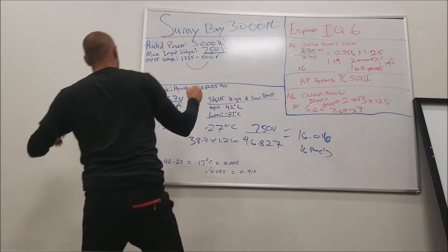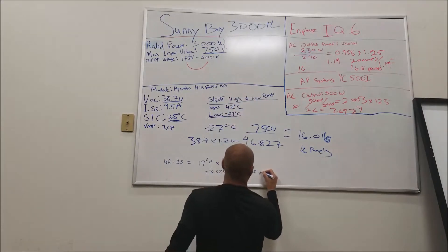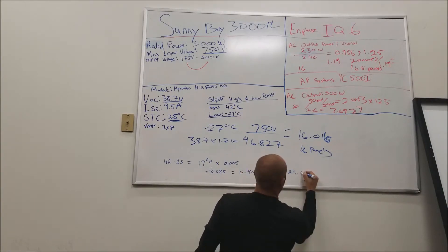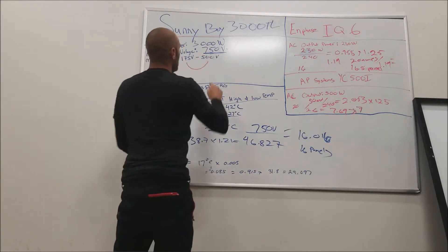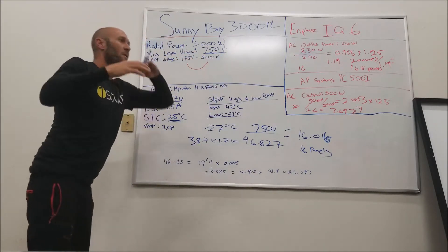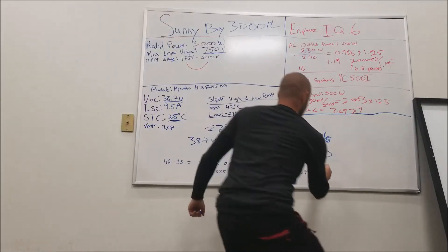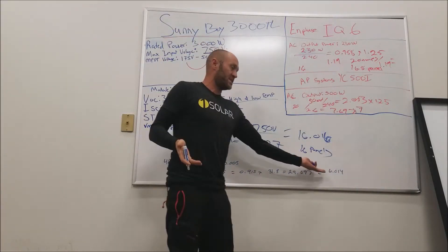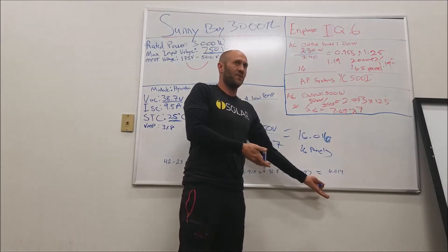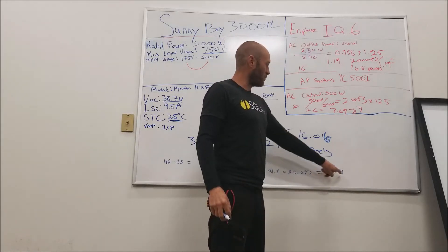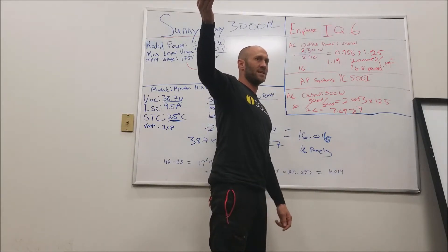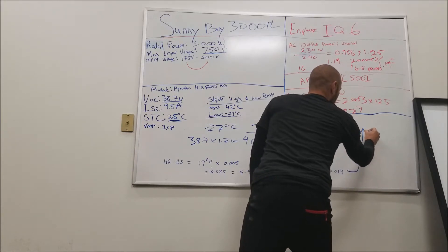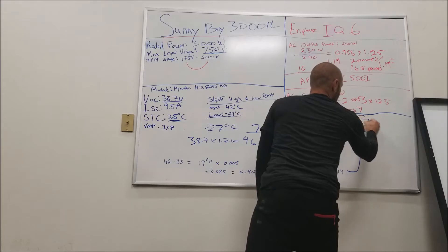Take that 0.915 and multiply by your VMP of 31.8 volts: 31.8 times 0.915 equals 29.097 volts. Now divide the minimum MPPT voltage of 175 by 29.097. That gives you 6.014. Even though the calculator shows 6.014, that 0.014 makes it higher than six — so you cannot do six panels. You have to round up to seven.